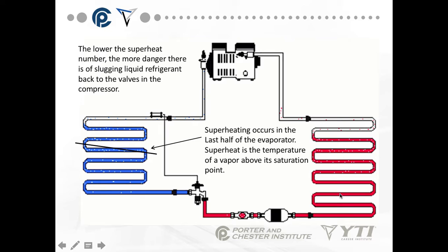Superheating, which is the opposite of sub-cooling, occurs in the last half of the evaporator. Superheat is the temperature of vapor above its saturation point. We're absorbing heat through the boiling process — a latent heat change, going from liquid to vapor — and still absorbing some heat as the refrigerant leaves the evaporator. The lower the superheat number, the more danger there is of slugging — sending liquid refrigerant back to the valves of the compressor. Superheat in most systems is between 8 and 12 degrees.